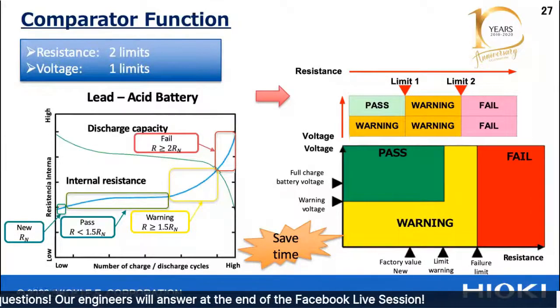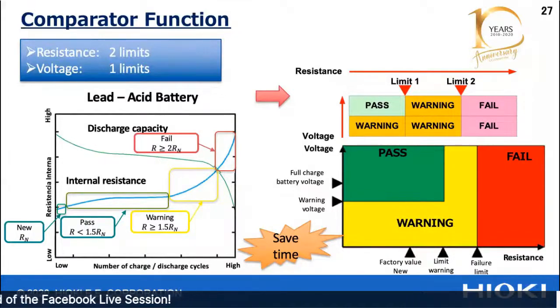As for voltage, the limit for the warning condition is 90% of the nominal voltage of the battery. So let's say you measure the battery and get 12 volts, then you can input 90% of that. Anything below that will be a warning condition.